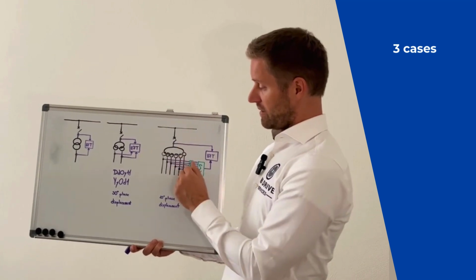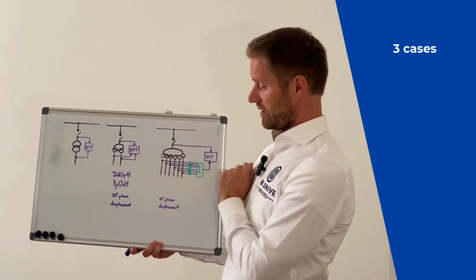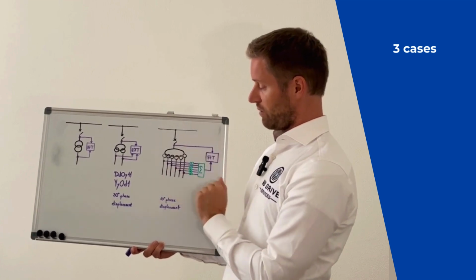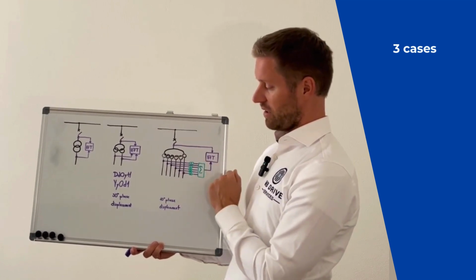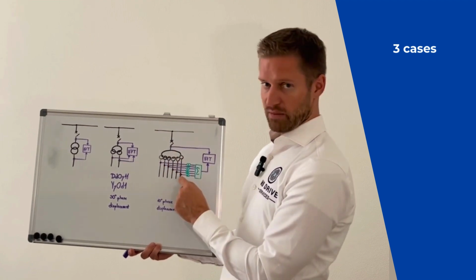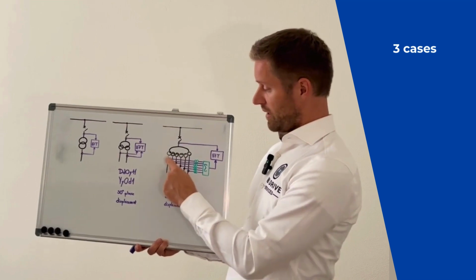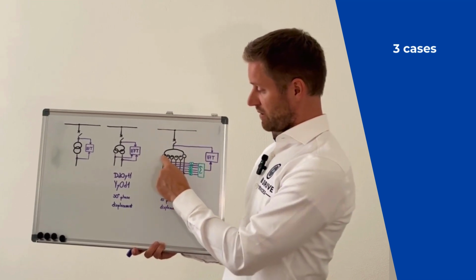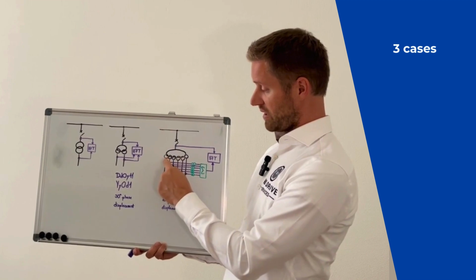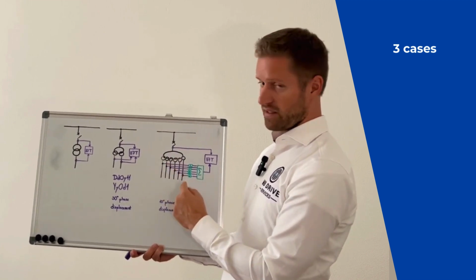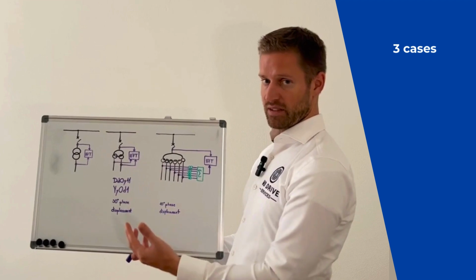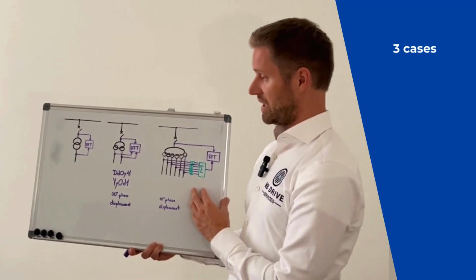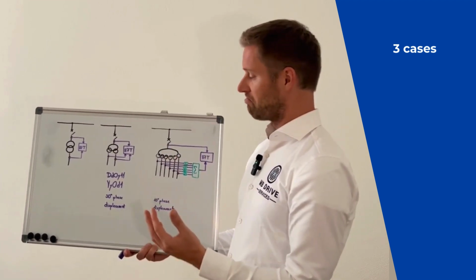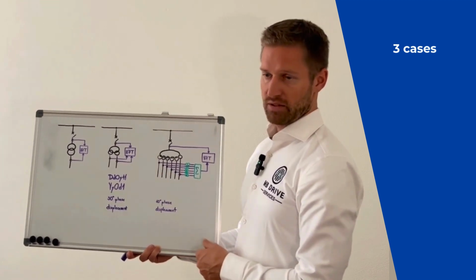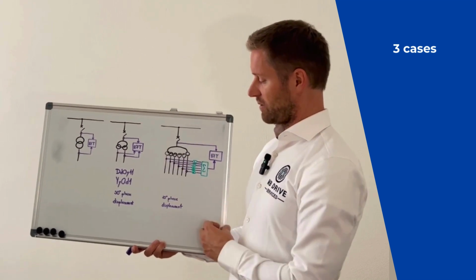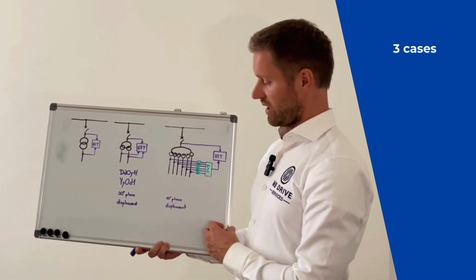What we can see is that as the number of secondary windings is increasing, we need more components besides the relay itself. We have, of course, the current measurement. So on the secondary side, if we have 6 secondary windings, we need 6 sets of CTs. So the number of the current transformers is increasing. This might also cause some considerations about the reliability. As the number of components goes up, of course the reliability goes down.